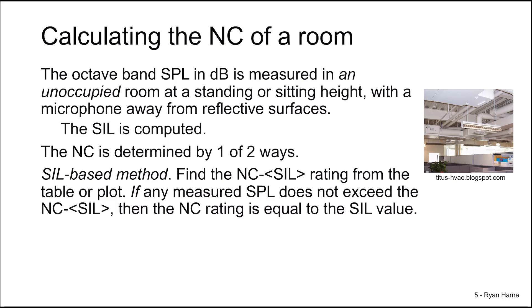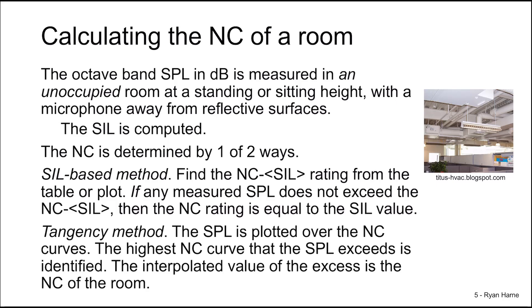Now, if some of the SPL readings do exceed the NC-SIL, then we use the tangency method. The SPL is plotted over the NC curves. The highest NC curve that the SPL exceeds is identified, and then we interpolate over that exceeded amount to compute the NC of the room. An example of computing the NC of a room is needed to understand how to do this in practice.